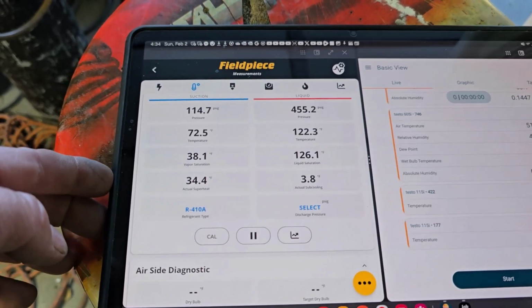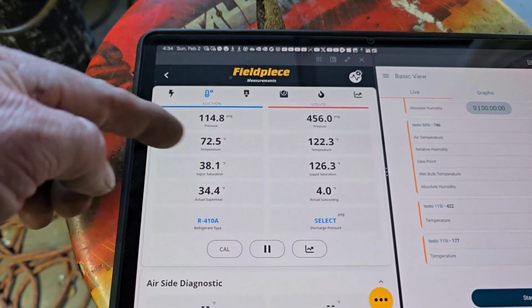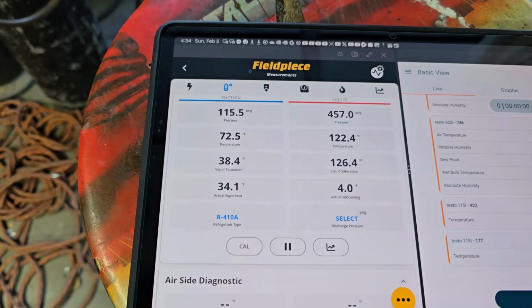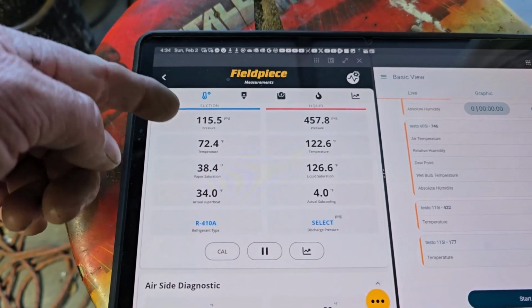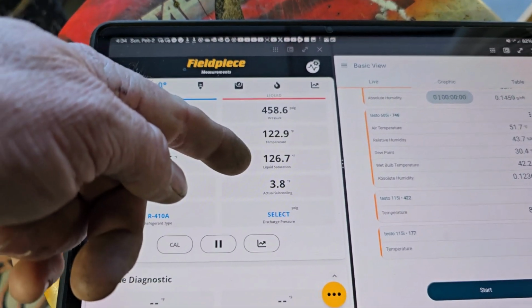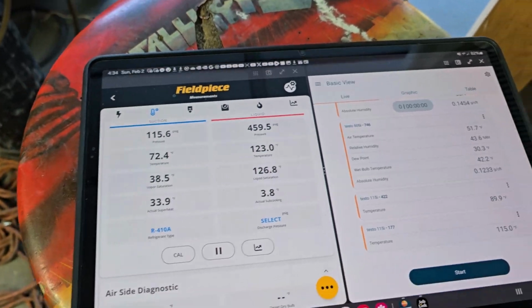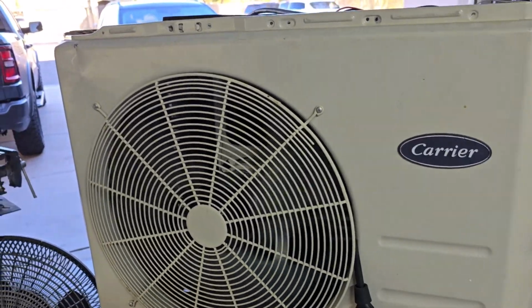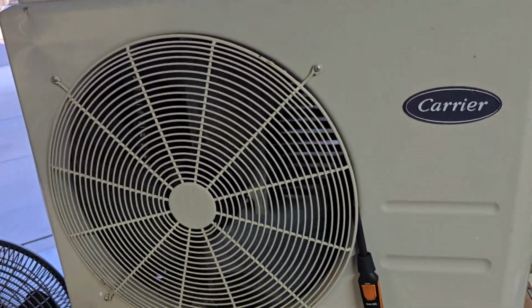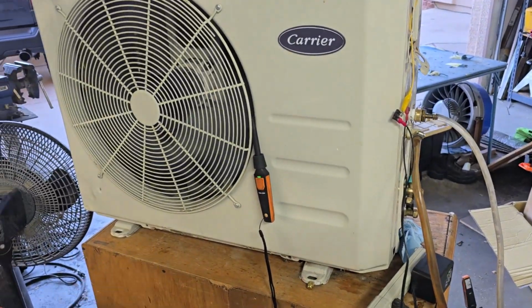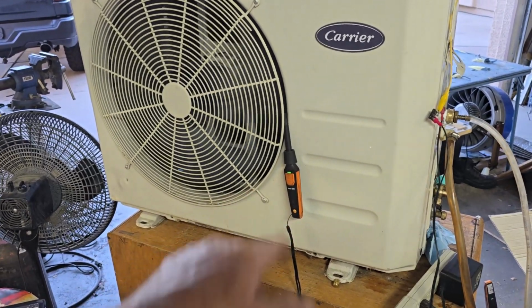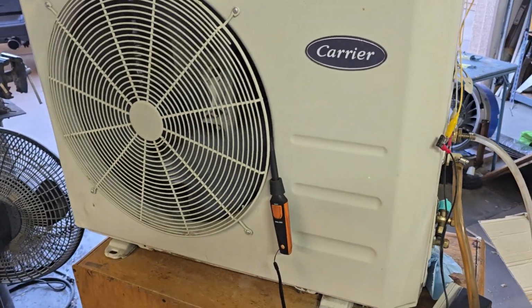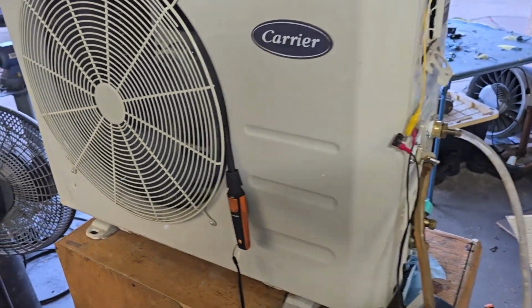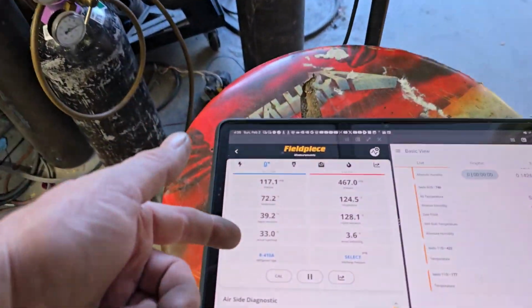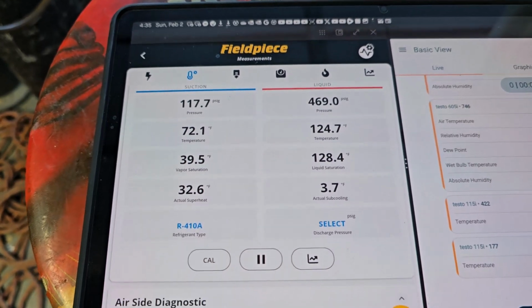Yeah. So I almost could have added just a little bit of refrigerant. See, it's got a little bit of superheat there. Suction pressure is just a little low. Only got a couple degrees of subcooling. And once again, I just throw it together, kind of come out with the coil, just running off the top of my head. Capillary tubes. This time I used the capillary tubes that were in the unit the compressor came out of, so I didn't need to calculate this one. And it works. I know if I add a little bit of refrigerant, it'll bring down that superheat.